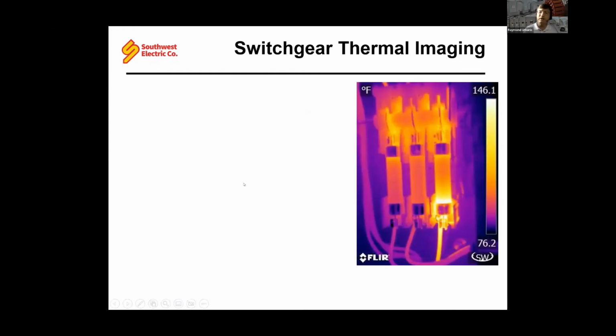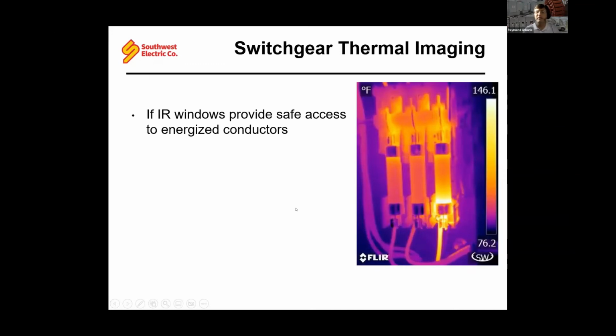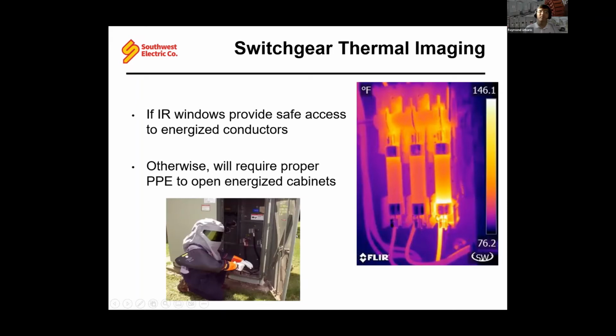You can also do the same thing for your switchgear, and you can do a quick scan to see if any particular phase is seeing any kind of hotspot, as you see here in phase C of this fuse. So if you install IR windows, which we also highly recommend, you can do these IR scans in your switchgear while the doors are closed. You don't have to have the PPE, and you can get this information whenever you want, again, on demand. And otherwise, you're going to be suiting up like this guy in order to take these scans.